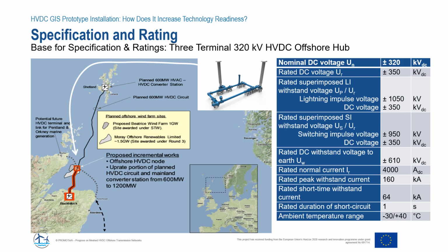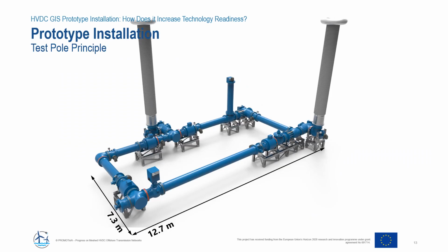If we have a rated voltage of 350 kV, we have a superimposed lightning impulse voltage of 1050 kV, switching impulse of 950 kV, and 4000 amps rated current. The test pole itself looks like this. It is a rather large GIS ring with 2 SF6 bushings. These bushings are used to connect the high voltage from the test lab with the test pole itself.